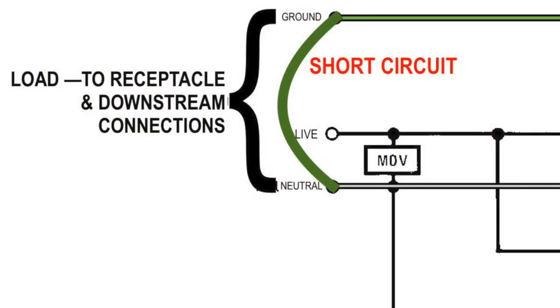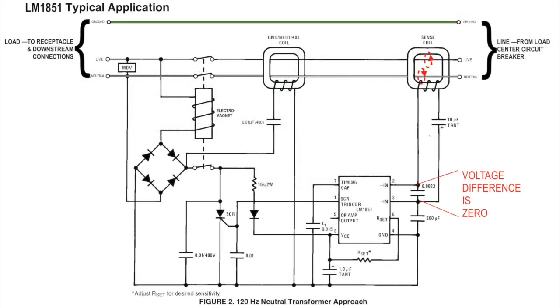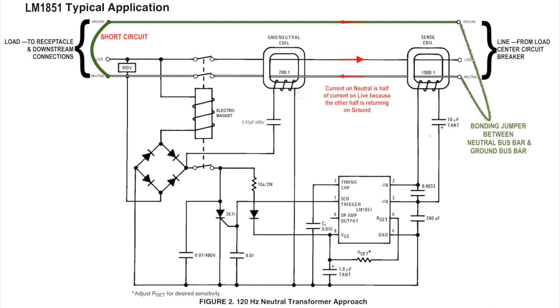GFCIs have a second function, that is to detect a short between ground and neutral. As mentioned before, during normal conditions, current on the live and neutral are exactly the same. That's because the resistance of the live and neutral conductors from the load center are exactly equal. But imagine if the ground and neutral conductors were shorted together downstream of the GFCI. This would defeat the purpose of the ground conductor. Since the neutral and ground are connected together in the load center, shorting them together downstream puts both the ground conductor and the neutral conductor in parallel, splitting the current between neutral and ground.